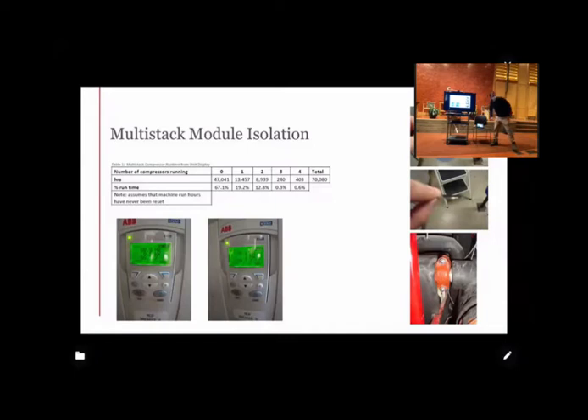But before we adopted the isolation of the two heat pumps, we had data from the prior winter showing worst case outside temperatures, and the data from the unit showed that 99% of the time, we only needed two to take care of the main heat load. Yeah, and so after that first winter on just one module, it was like, okay, well, it's fine. You know, we didn't have any issues.